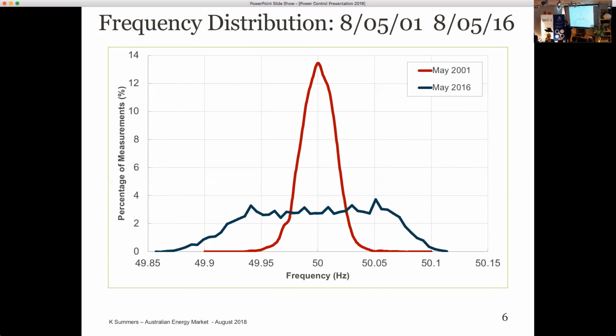Originally, our frequency band was 49.5 to 50, 49.1 to 50, 49.9 to 50.1 was the original band, but we had mandatory governor deadbands or mandatory governor response kicking in, and the largest deadband that you could have was plus minus 0.05, I think. So that would be consistent with that. It's documented in one of the papers that I put out in 2016.